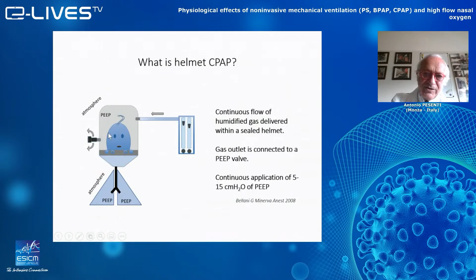But the fresh gas flow at different FiO2s goes to the helmet and goes out to the atmosphere through a valve. If you have an infectious patient, like a COVID-19 patient, you can put a filter at the exit to avoid contamination of the ambient. And the valve generates a PEEP level according to what you need, actually what your patient needs.